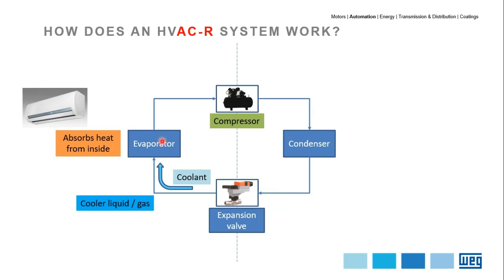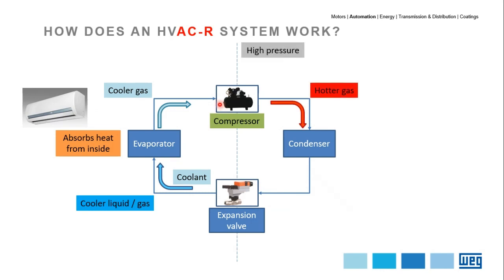The analogy for the evaporator is the air conditioner you have inside your home. Instead of thinking that you are blowing cold air inside, you are actually removing heat from the inside. Once the coolant crosses the evaporator, it evaporates — going from liquid state to gas state, but still a little cool. Once it reaches the compressor, it changes temperature because the compressor, as the name says, compresses the gas and moves it to the high pressure side.